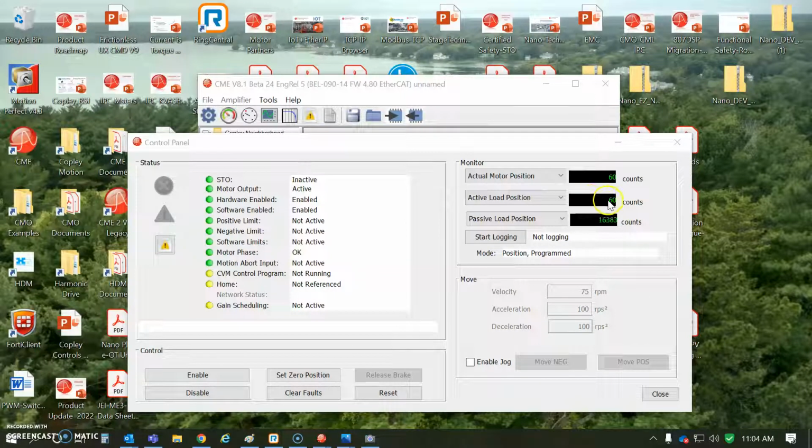And then the motor itself has an absolute encoder, and if I power up at this position, both are at zero, plus or minus a little bit. I set the wrap in this, trying to get both to zero. I think no matter how slow I move, I'm not able to get them both to zero. So maybe there's a little offset to get the count to go to actual zero. I'm just moving the motor encoder and then just reading the load. Gee, within 10 counts. I mean, that's pretty good.